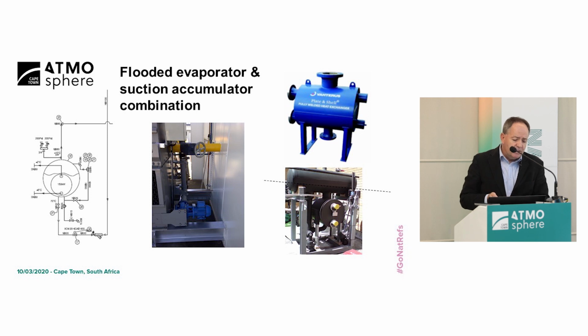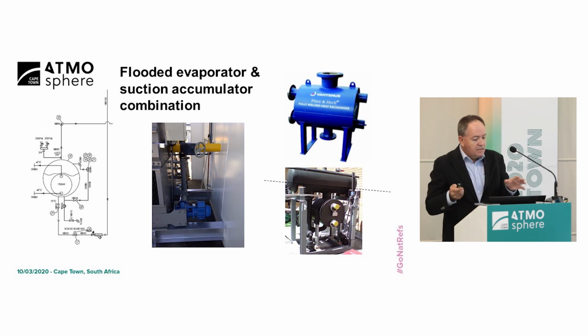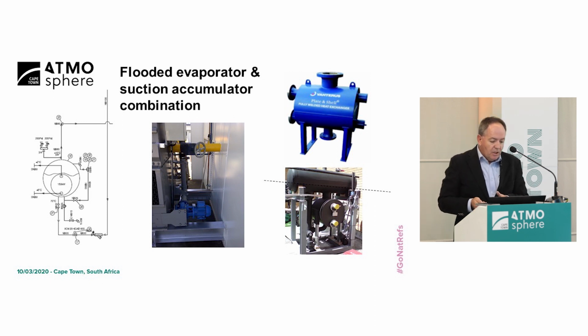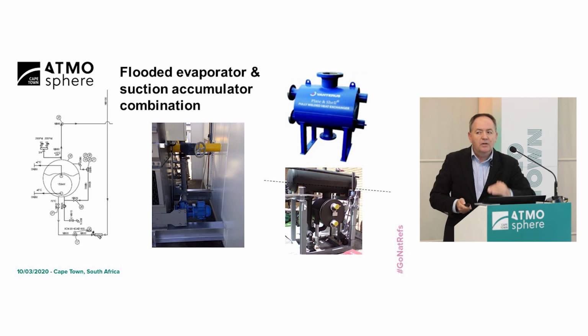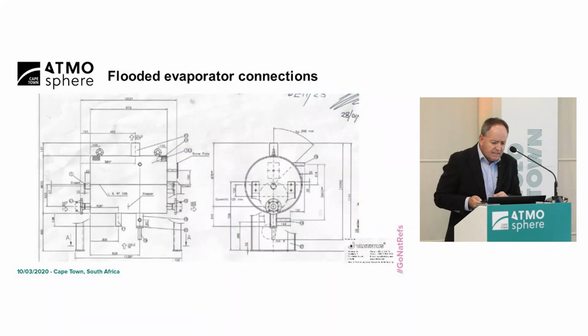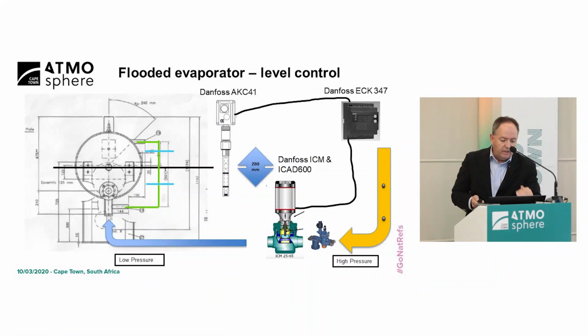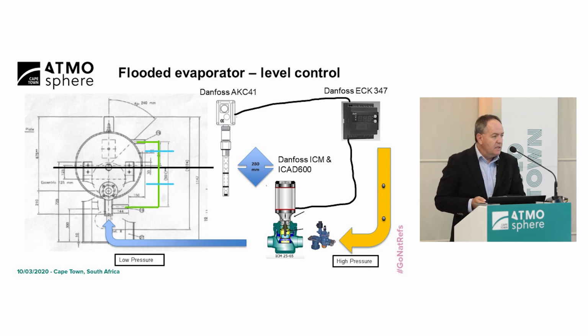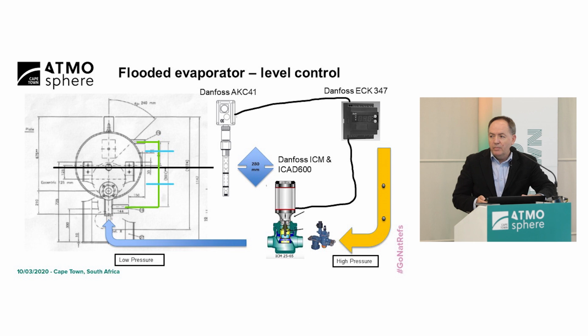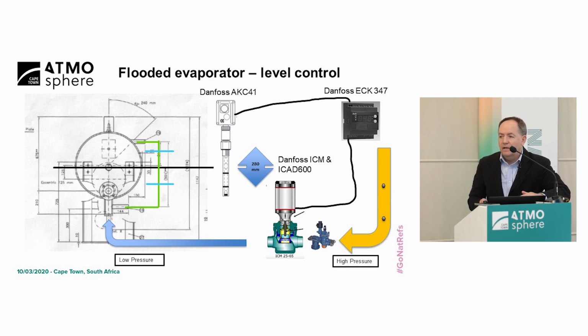Key in this case was the evaporation with our heat exchanger. On the low pressure side was a unit from Vahterus, a suction accumulator heat exchanger combination. You can see on the illustration the circular heat exchanger was flooded, and the alternative was a heat exchanger with an accumulator above it. So you can see the blue unit is a lot more compact. That's the shop drawing. The key in this case was a level sensor maintaining the ammonia level in that heat exchanger. The level sensor sends a signal to the controller, which opens the expansion device and feeds liquid into the heat exchanger. So we're maintaining that black line, that level, constantly.